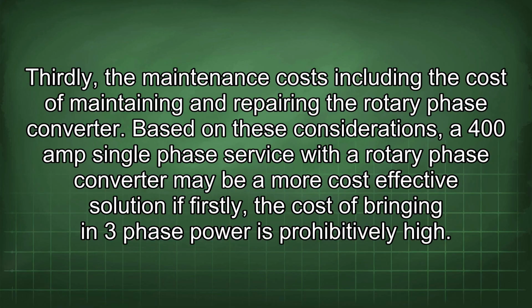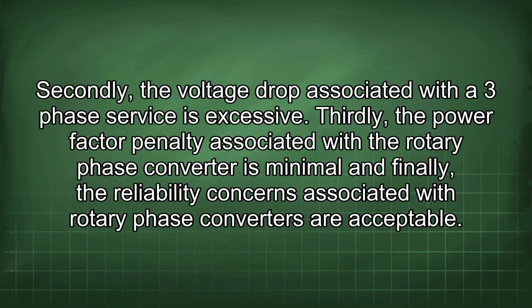Based on these considerations, a 400 amp single-phase service with a rotary phase converter may be a more cost-effective solution if, firstly, the cost of bringing in three-phase power is prohibitively high. Secondly, the voltage drop associated with a three-phase service is excessive. Thirdly, the power factor penalty associated with the rotary phase converter is minimal. And finally, the reliability concerns associated with rotary phase converters are acceptable.